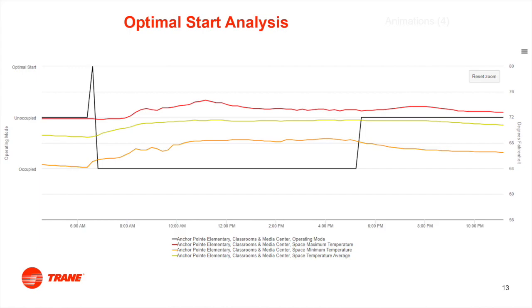Anyway, so on the left here, we have our modes: unoccupied, which means off; occupied, which means on; and then we have optimal start here. And then on the right, we have temperature. So let's add in some data here. We see what the mode is doing - it goes from unoccupied, goes into an optimal start mode, and then hits occupied for the entire day.